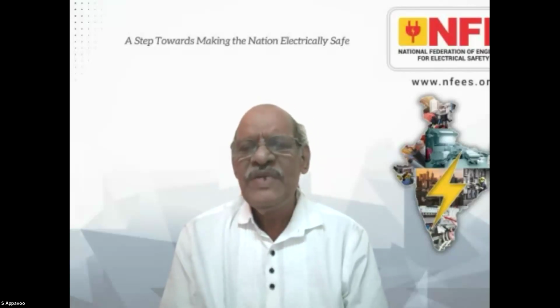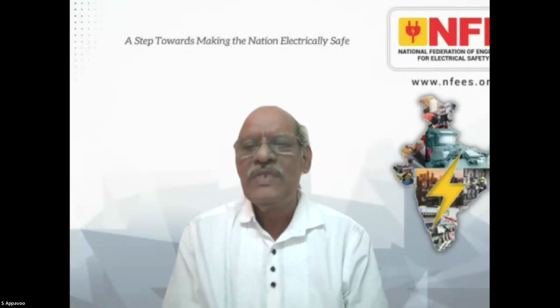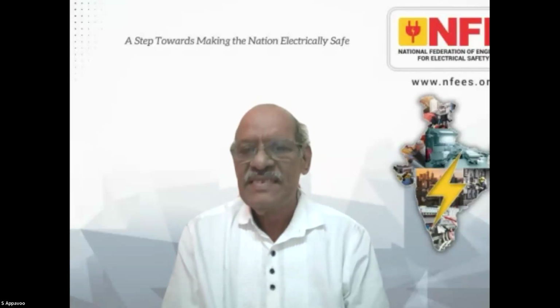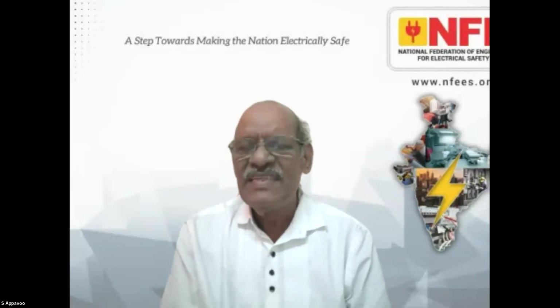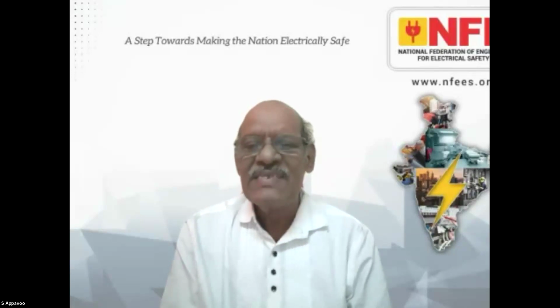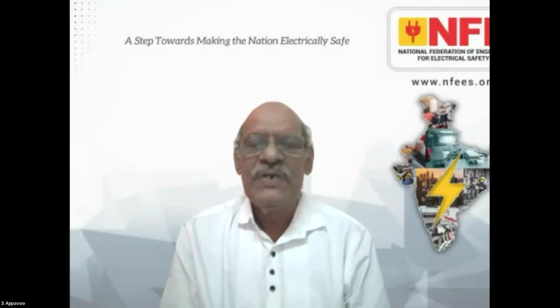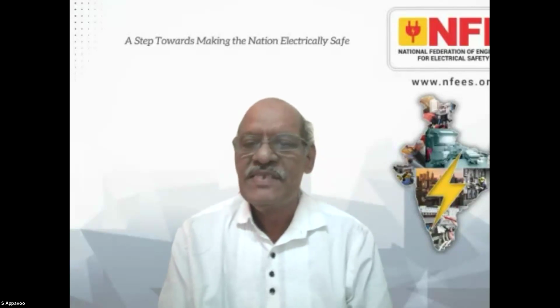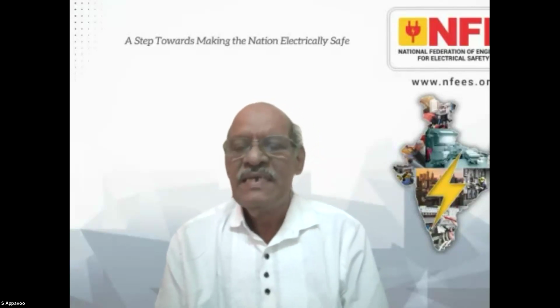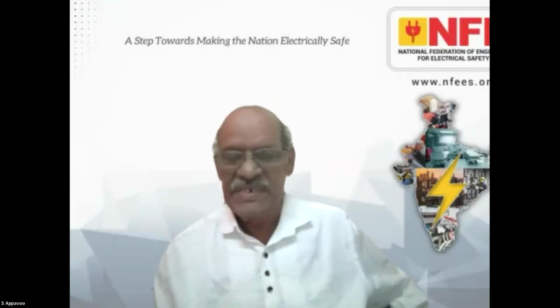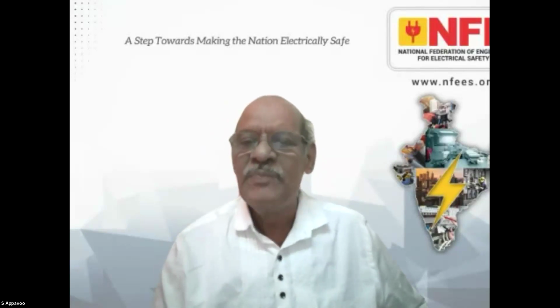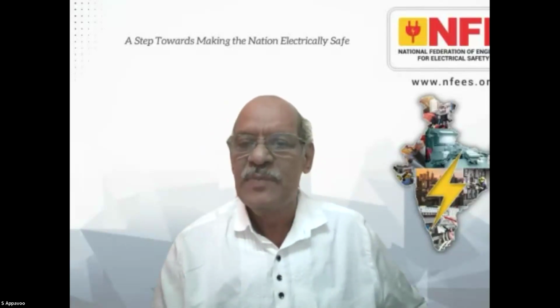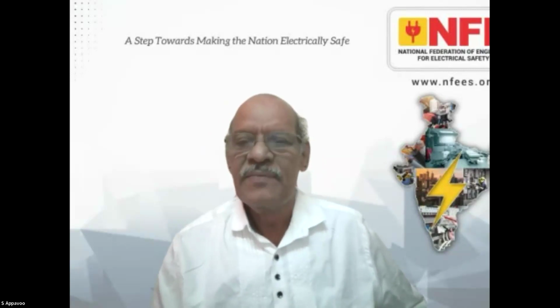So this is why we provide a strip around the building, the type B earthing system itself. We do not think that the electrode alone is the earthing system. Strips give a very good earthing system for reference and to discharge the lightning current equally around the building, instead of a single pointed contact or two or three points of contact.